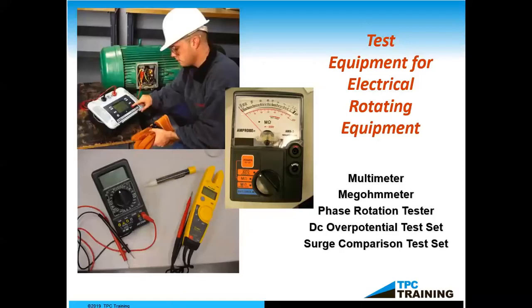So a little bit of test equipment that we're going to need to be able to troubleshoot this motor. And some of this might look a little bit sophisticated, but I do want to mention that the yellow meter from Fluke is a T5-600. So that is basically your basic multimeter. It'll test volts for you, it'll test amperage, and it'll test resistance. So that's a great meter.